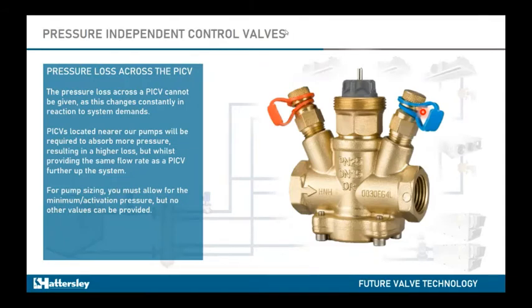So as I mentioned before, the pressure losses can be read between the red and blue valves, test points on the valve itself. Critically, when we commission, we need to scan the entire system. We need to add those results to your flow charts and obviously the commissioning report.